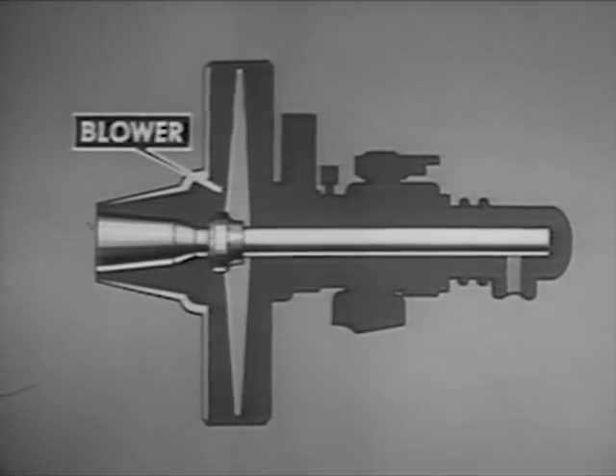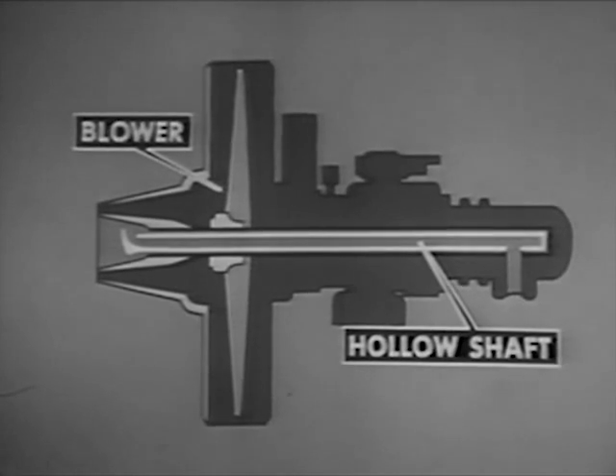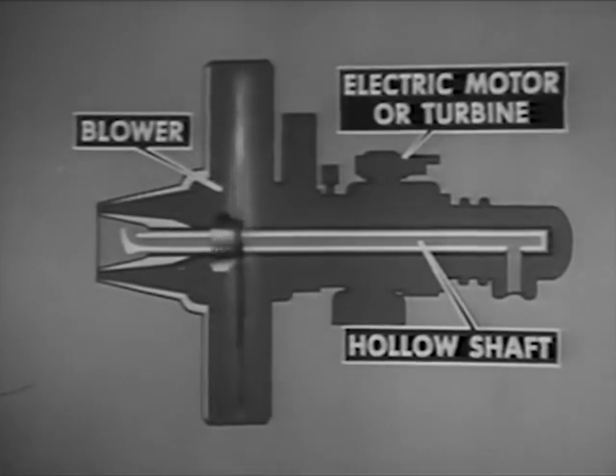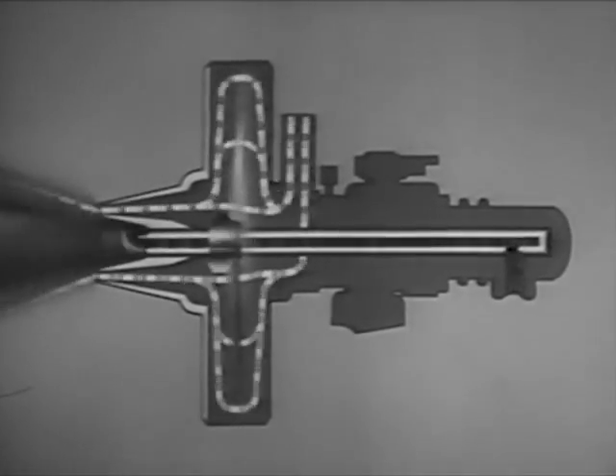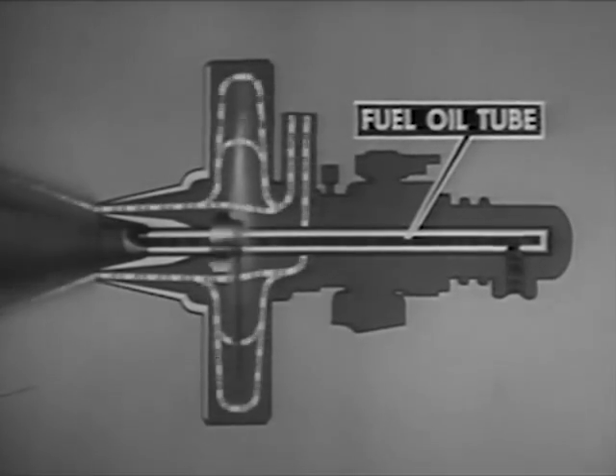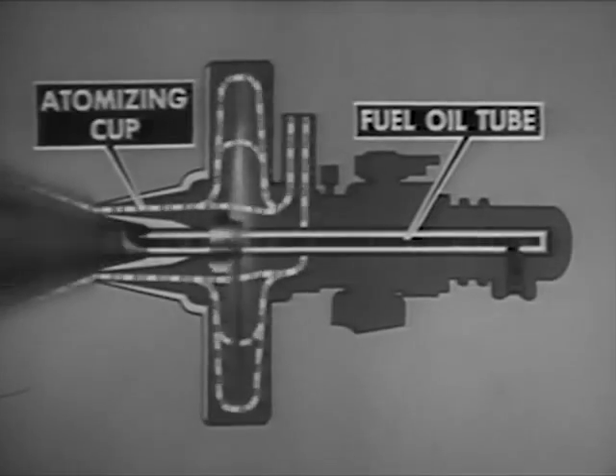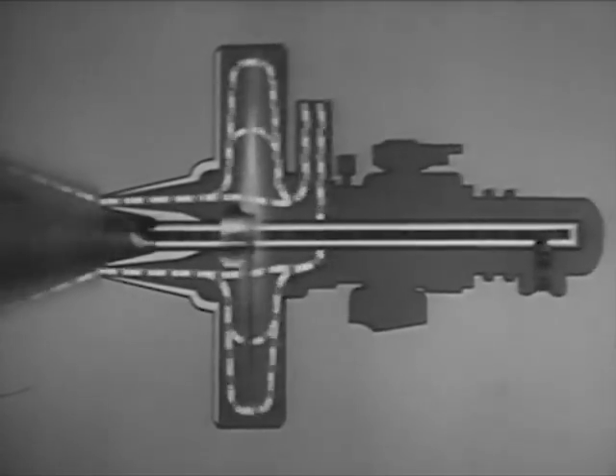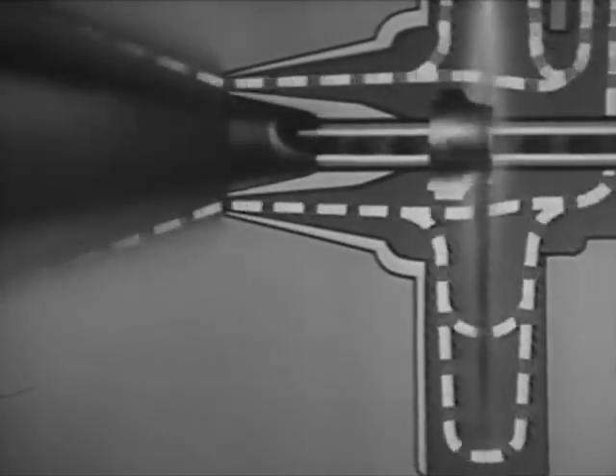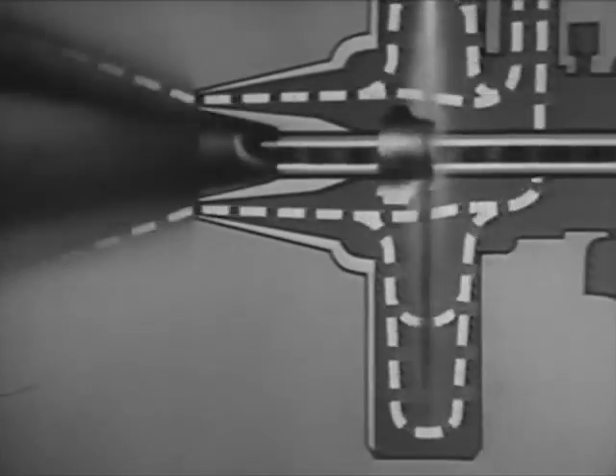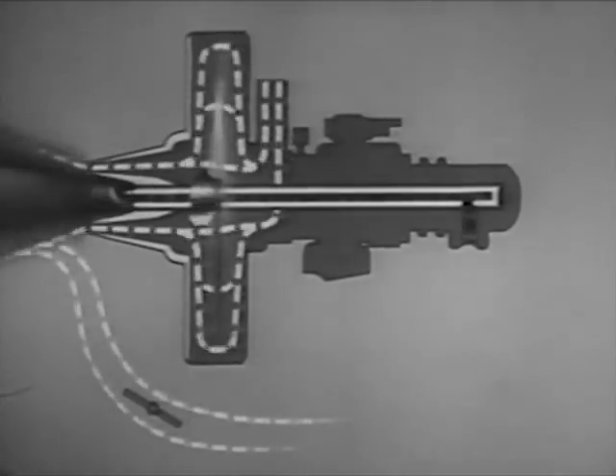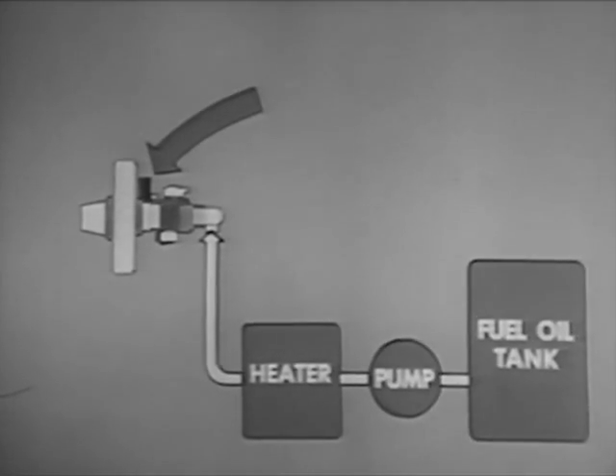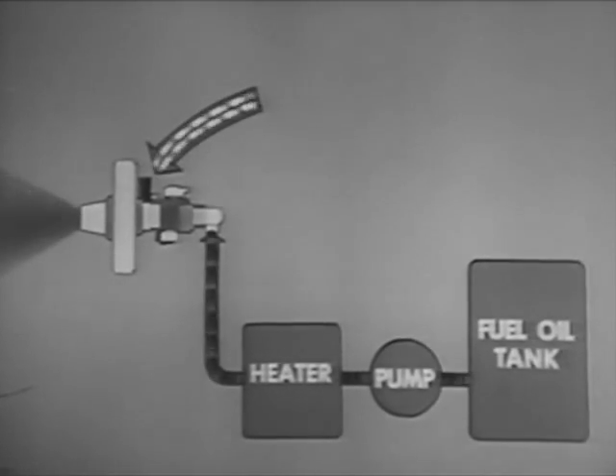In the rotary cup burner, a fan or blower is mounted on a hollow steel shaft. An electric motor or steam turbine turns the shaft and blower at high speed, providing a blast of air around the burner nozzle. The oil, under low pressure, enters through a stationary fuel oil tube inside the rotating hollow shaft and is discharged into the rotating atomizing cup. Centrifugal action forces the oil against the inner surface of the atomizing cup and causes the oil to leave the rim as a hollow cone. The meeting of the oil and the air from the blower further atomizes the oil. Additional air, needed for proper combustion, enters through an air door in the furnace wall. As in all burners, you control the firing rate by controlling the amount of fuel oil and air going to the burner.